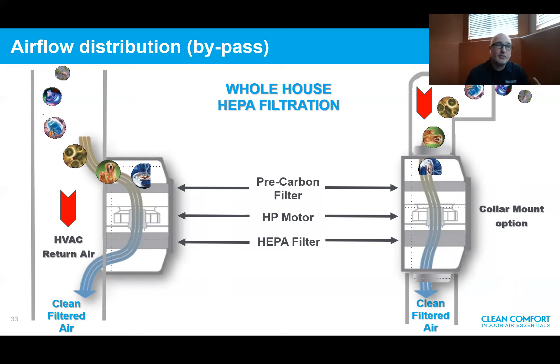One important consideration: the filtration process is not on and off. It's recommended to run your forced air system in conjunction with your HEPA system 24 hours a day to maximize the filtration process. For example, if I have 100 particles and I pick up 20% of them, filter them through the three-stage filtration, then reintroduce clean air into the return, I go from 100 to 80. On the next pass, I pick up a portion of that 80%, pass through the HEPA system, and reduce further. With each pass, particles are reduced — so if you run it on and off, you're not maximizing the filtration process.